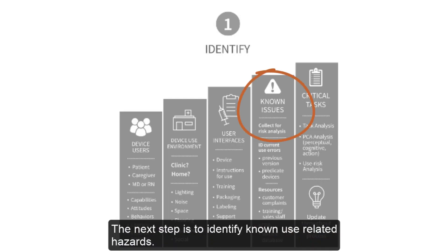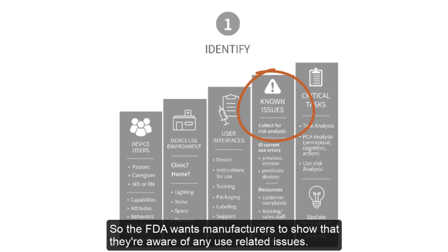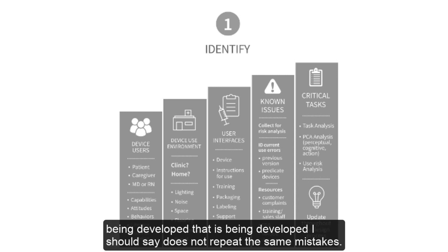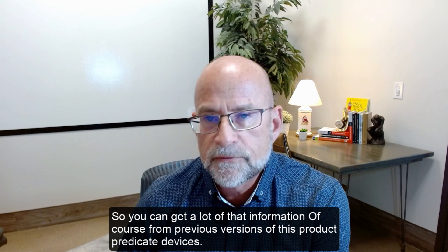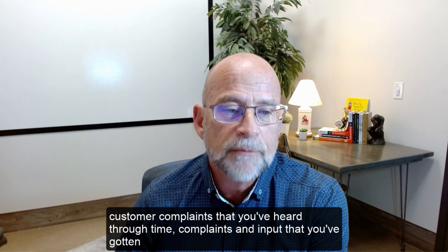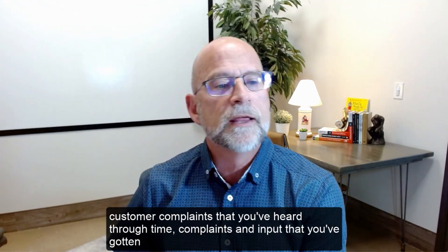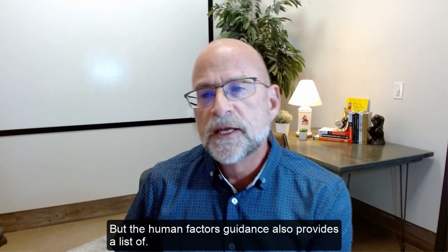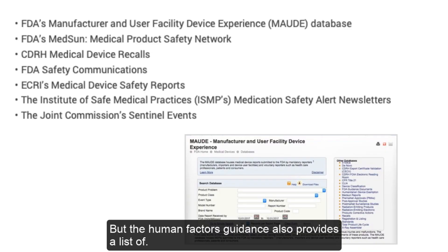The next step is to identify known use-related hazards. The FDA wants manufacturers to show they're aware of any use-related issues present in similar or predicate devices, and that the device being developed does not repeat the same mistakes. You can get this information from previous versions of the product, predicate devices, customer complaints, and input gathered through training, sales staff, and similar sources.